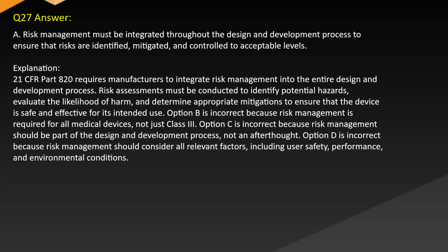Answer A. Risk management must be integrated throughout the design and development process to ensure that risks are identified, mitigated, and controlled to acceptable levels. Explanation: 21 CFR Part 820 requires manufacturers to integrate risk management into the entire design and development process. Risk assessments must be conducted to identify potential hazards, evaluate the likelihood of harm, and implement appropriate mitigations to ensure that the device is safe and effective for its intended use.